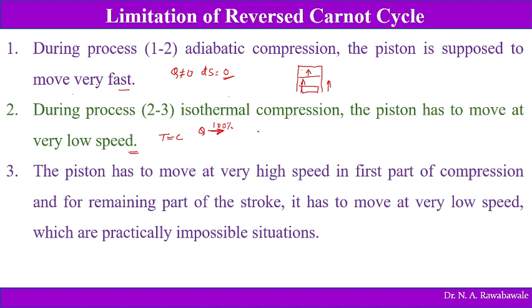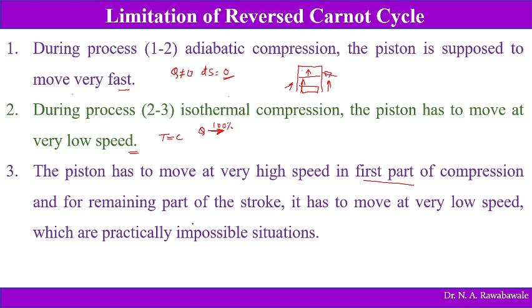So part of the piston movement has to be made at a very fast speed, and part of the movement of the piston has to be made at very slow speed. Say for example, this is the cylinder and the piston is moving from BDC to TDC. Partly the piston has to move at a very high speed, and partly it has to move at very slow speed. In the same stroke it is not possible to have two different speeds, and practically this is not possible. The piston has to move at a very high speed in the first part of compression during adiabatic compression, and for the remaining part of the stroke it has to move at a very low speed because it is an isothermal process, which is practically impossible. This is the limitation of the reversed Carnot cycle, and because of this the reversed Carnot cycle cannot be used for producing refrigerating effect or to manufacture a refrigerator working on it. This is the major demerit.